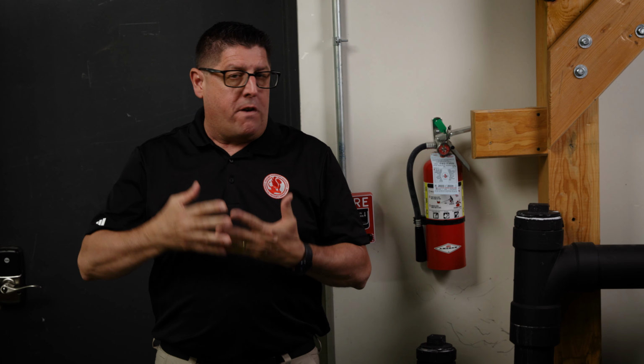This type of fire extinguisher that we have is just a normal fire extinguisher in a building. It's what's called an ABC fire extinguisher, which puts out various types of fires, and they need to be placed within 75 walking steps from the next one. So if I'm standing in one spot, 75 foot that way and 75 foot that way, better be a fire extinguisher. And again, not blocked. If we're in a commercial cooking space, any spot that cooks in a commercial environment, then those fire extinguishers need to be a type K fire extinguisher for kitchen and be within 30 foot of every cooking appliance.